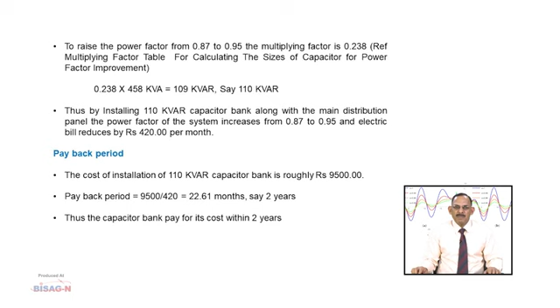Considering the payback period, it is calculated as below. The cost of installation of 110 kVAr capacitor bank is roughly 9500. The payback period equals 9500 divided by rupees 420 equals 22.61 months, say 2 years. Thus, the capacitor bank pays for its cost within 2 years.